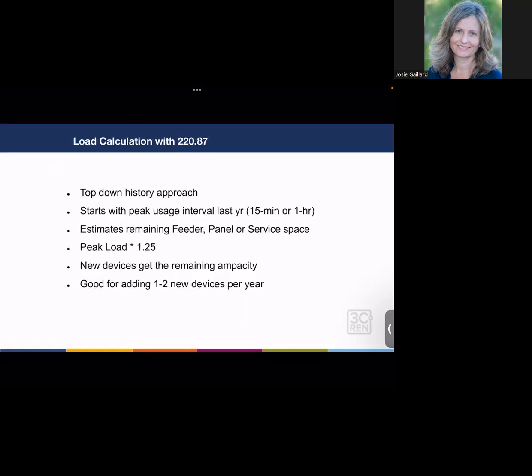Okay, so let's talk about 220.87. It's this top-down approach using their historical electrical load for the last year. We want to look at something called interval data. So their peak usage, looking at 15-minute or 1-hour intervals. So for folks in SoCal Edison or PG&E territory, you have a smart meter, I'm assuming you do anyway. And for that smart meter, your data gets reported to the utility either in 15-minute or 1-hour intervals.